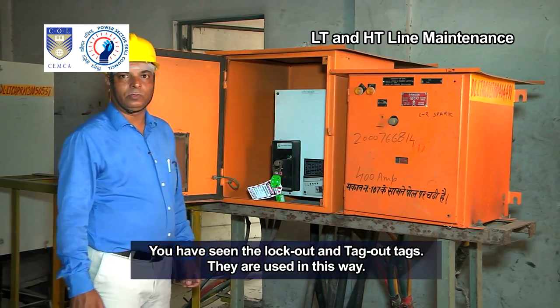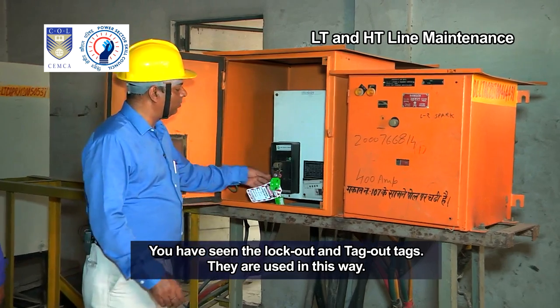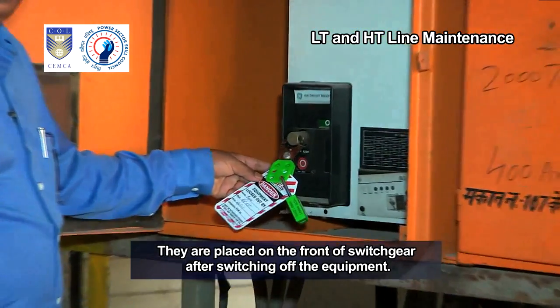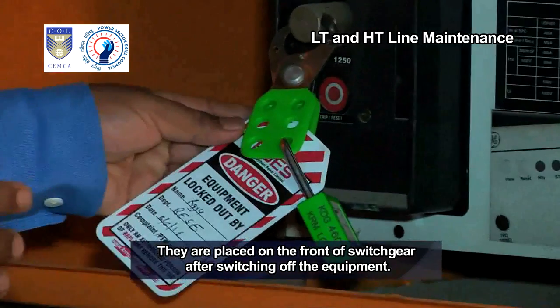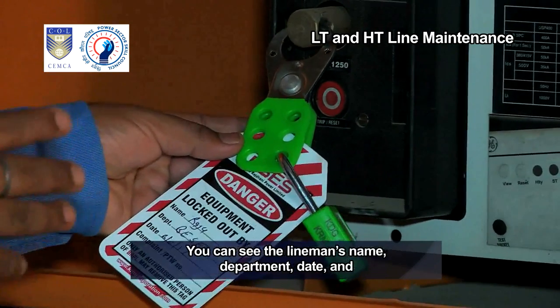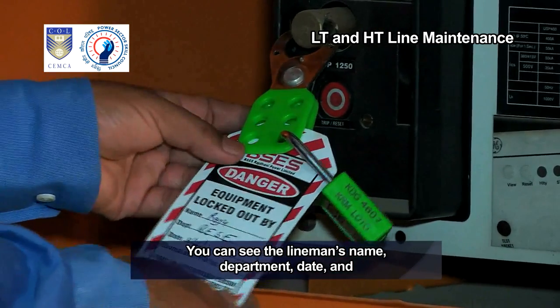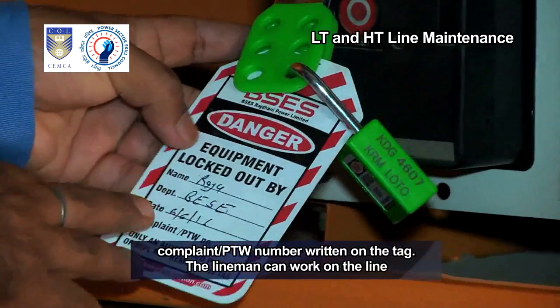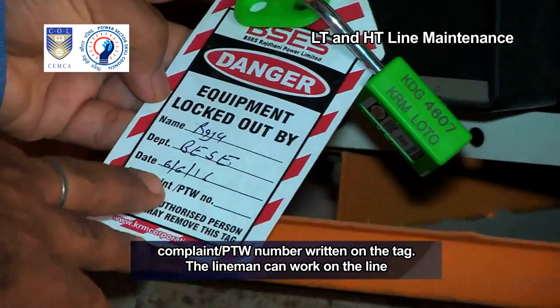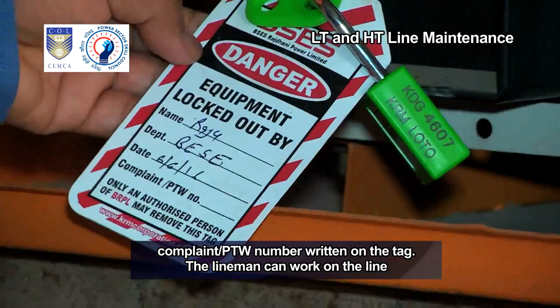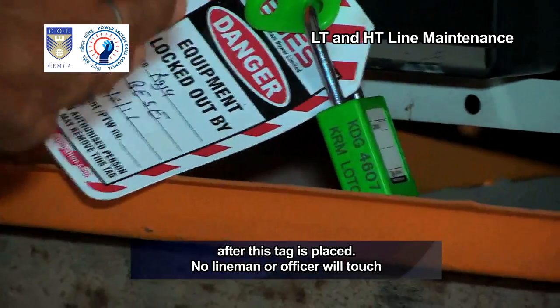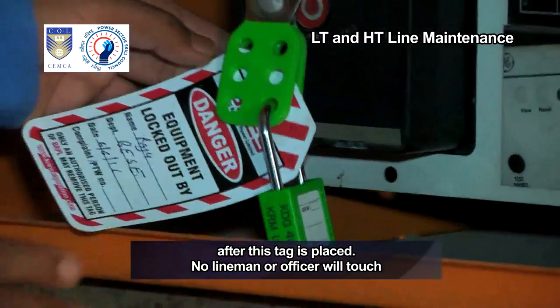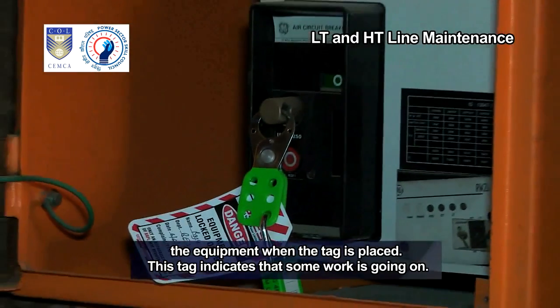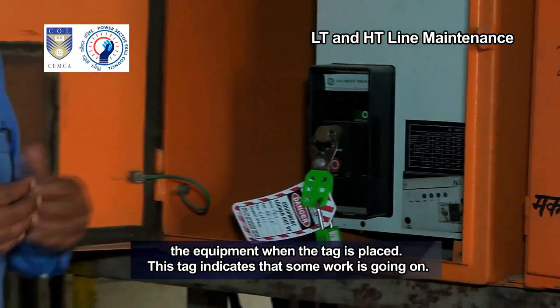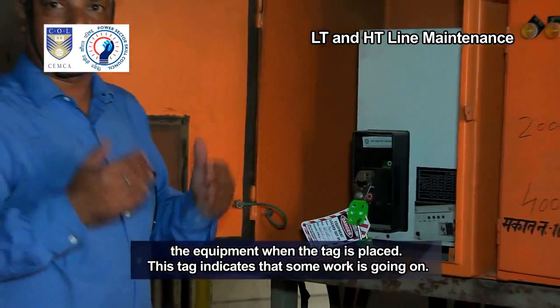You have seen the lockout and tag-out tags. They are used in this way. They are placed on the front of switchgear after switching off the equipment. You can see the lineman's name, department, date and complaint, PTW number written on the tag. The lineman can work on the line after this tag is placed. No lineman or officer will touch the equipment when the tag is placed. This tag indicates that some work is going on.